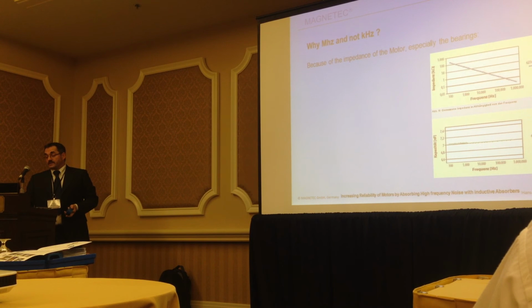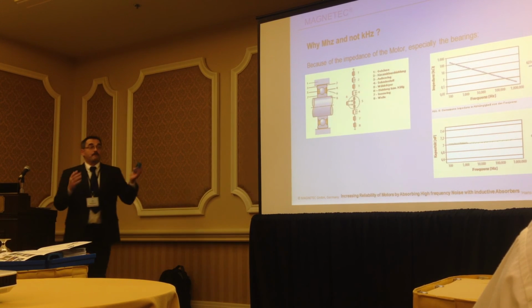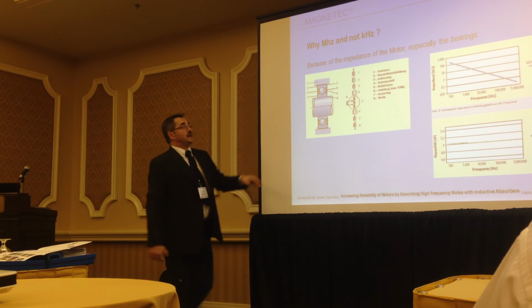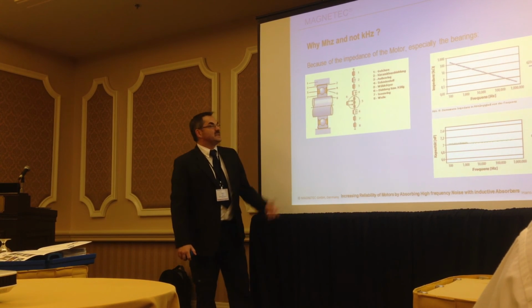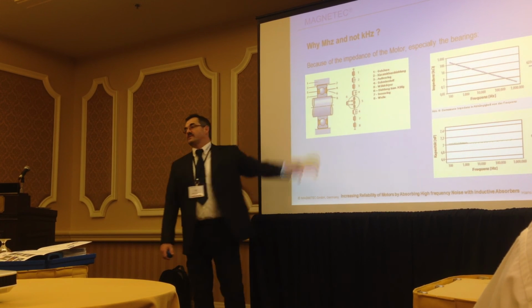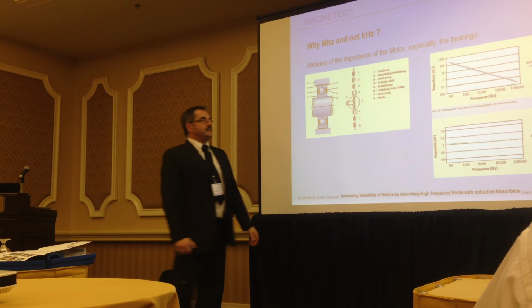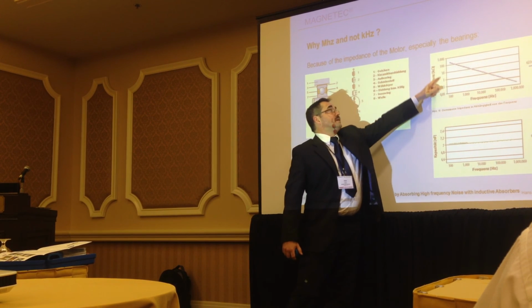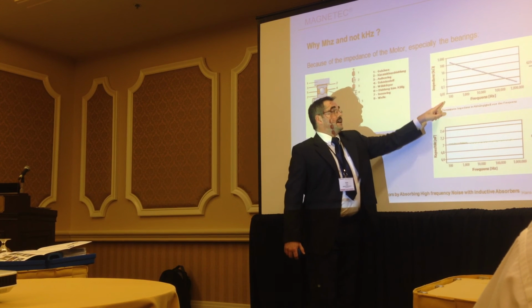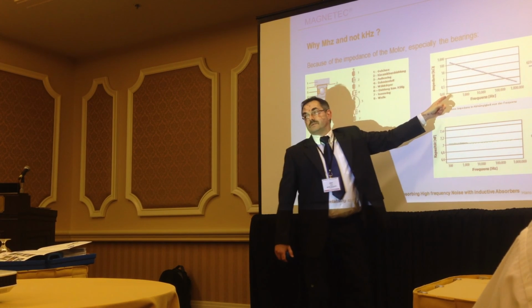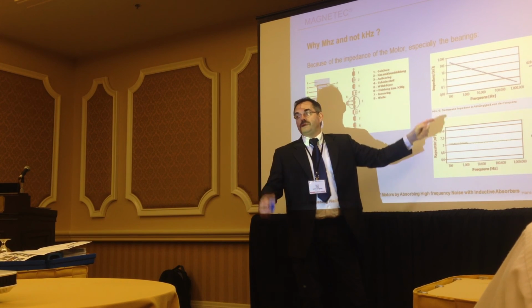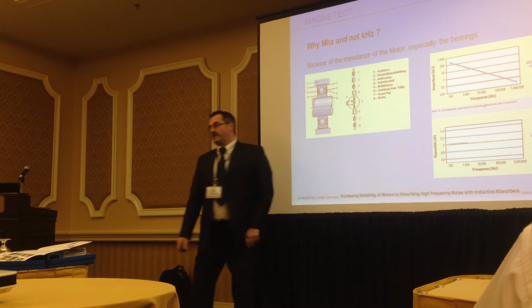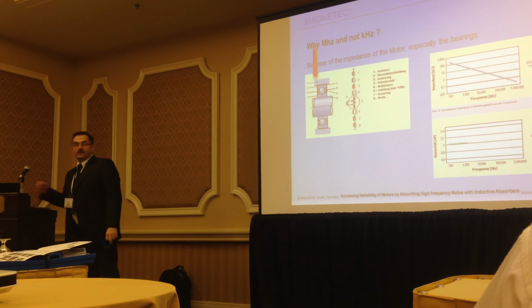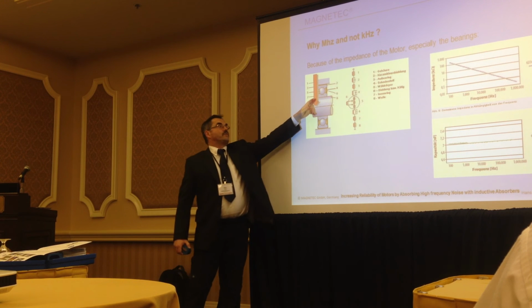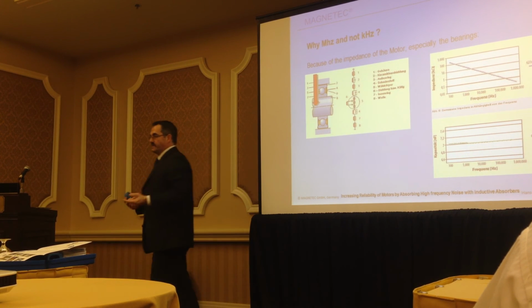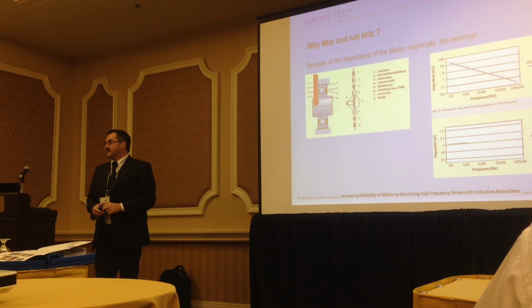Why megahertz and not kilohertz? That's very simple. If you understand it one time, a bearing on a motor, or most insulations of the motor, you can describe by very complex things. It's much easier at the end. Just forget that this is a bearing, just think this is a capacitor. It's nothing else. That means a capacitor has at low frequencies a very high impedance, we see kilo ohms. Yeah? And when you are in the megahertz range, you are at a few ohms. So that means the bearing has a low impedance at high frequencies. So the current is just jumping over that and gives you a welding spot on the outer race. So what happens? If the first welding happens, the bearing is getting noisy, that means pitting and everything, and then it's too late. That means you have to avoid this.